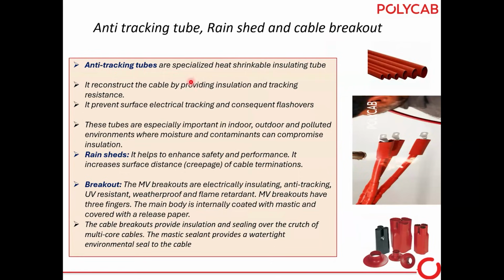First is the anti-tracking tubes. These are specialized heat shrink insulating tubes. They reconstruct the cable by providing insulation and tracking resistance, and prevent surface electrical tracking and consequent flashovers. These tubes are especially important for indoor, outdoor, and polluted environments, and they should be UV protected. Rain sheds are used to extend the creepage of the termination.